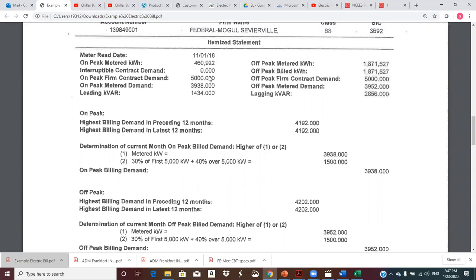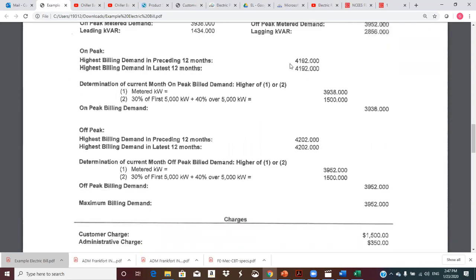Firm contract demand 5,000. That's on peak, and firm off peak 5,000. Metered, see, look, their metered demand was almost the same. On peak was 3938. Off peak was 3952. And look, their leading kVAR. This is, I believe, at the point of minimum load, at minimum demand, and the lagging is at maximum. And here they're remembering for the past 12 months. So the worst they've done is 4192 in the last 12 months. So that's the ratchet. They're just showing you right there.